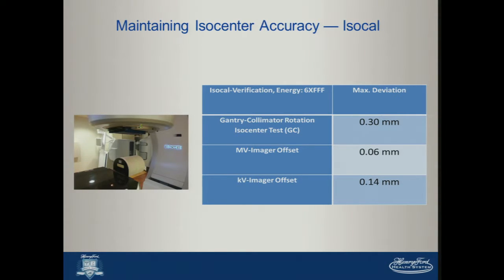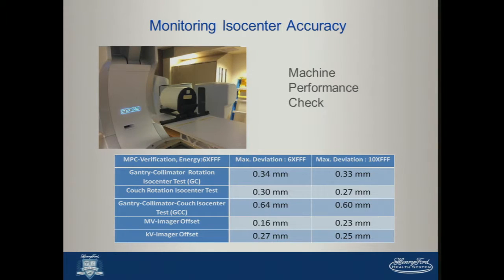So a valuable tool, and one that you would be recommended to get with your system. On a day-to-day basis, there's a machine performance check package, which I believe comes standard now with TrueBeam and the Edge system, but that'd be something to verify with Varian if you're considering buying a Varian machine. Our therapists actually run this, and it's checked by physicists daily, and it will report on the mechanical specs as well as the imager offsets, and we expect to see all those within the tolerances matching commissioning numbers.